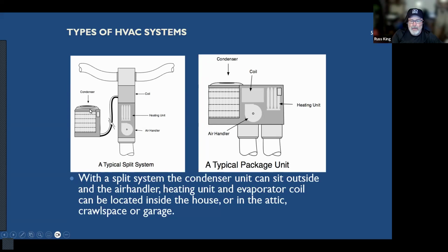There's going to be a condenser outside, and it might look like this, but you'll see some of the newer condensers, like the mini splits, are what we call a suitcase condenser. They're more tall and narrow, and the fan blows horizontally instead of the older style like this one, where the fan blows out the top. But it's still a condenser and it's still a split system. A mini split is a split system. There's ducted and ductless mini splits. There's an indoor unit, which can be ducted or ductless, and there's an outdoor unit. It's a split system because they're in two separate locations.